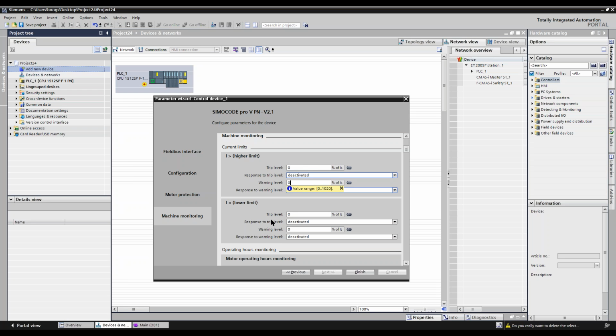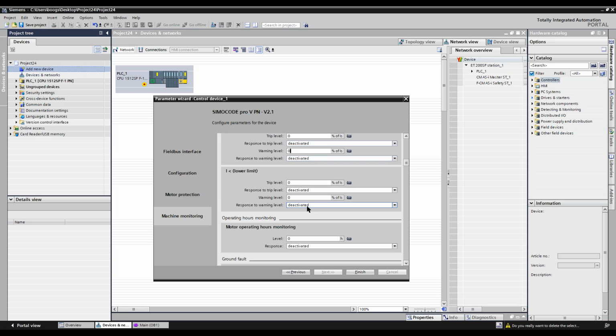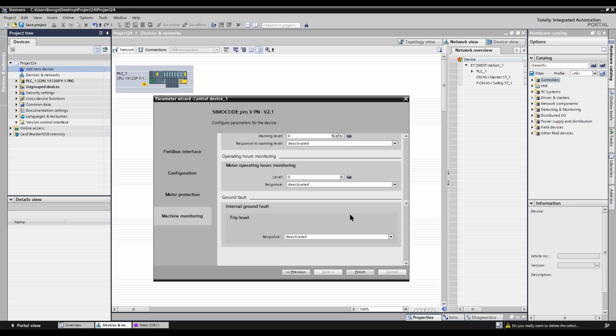And you remember I said if the industrial communication protocol, the Ethernet IP or the RS-485 communication, Profibus or Modbus RTU, gets cut, I could still let the SIMOCODE run because it can monitor and take care of things if something goes wrong within the process, because the PLC is not making the decision. The SIMOCODE is making the decision and just reporting back to the PLC to say, hey, do you want me to run or not? And if this PLC is gone and its communication protocol has been cut, then it can say, yep, I'm going to stop. So here's just a little level of redundancy. We're going to leave that alone for today's application.